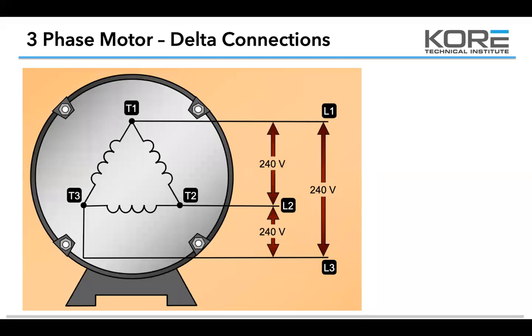So obviously, guys, if you're looking at this wiring diagram, I was on the phone a couple times yesterday with a few techs, and when you're dealing with three-phase, we're talking about checking the combinations. When you get your black and your red test leads out, the best way to check a three-phase motor is to go L1 to L3, look for your potential voltage there. Could be 208, could be 230. Make sure you look at the data tag on the motor. It's always going to be 208 or 230, even if the motor's 460. You might have a 277 high leg in some of the old Delta Ys.